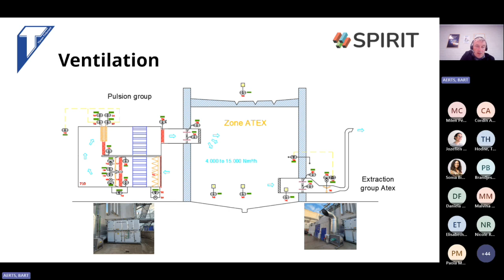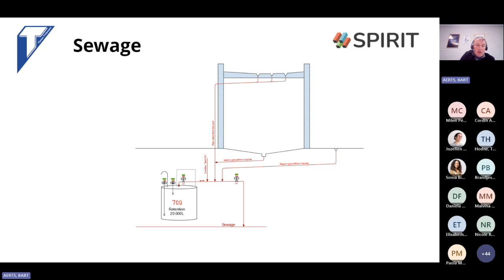Another point we worked on with the fire brigade and safety engineers was the risk of oil, in case of a leak, entering our sewage system. This is not allowed, and it's also very dangerous, because then your whole sewage system could contain pentane. That's why we connected our sewage system to a separate tank of 20,000 liters, so that in case of an alarm, all the water in the building goes to this tank.